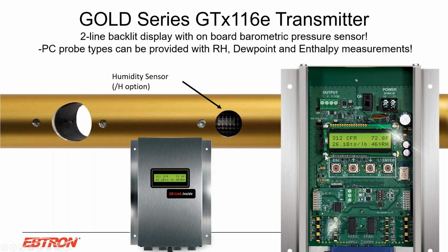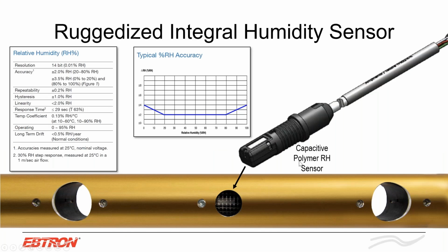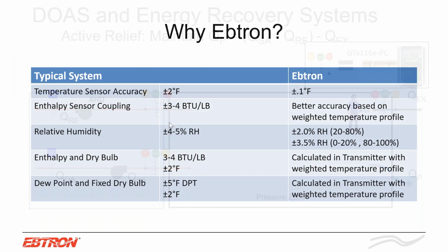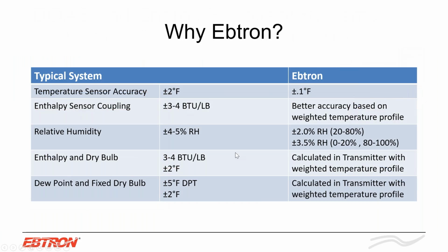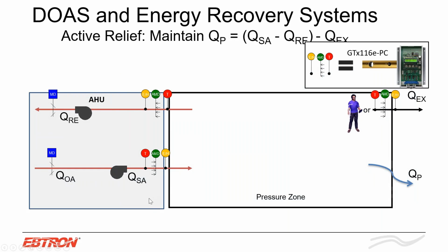So as an ATC contractor, this is a way to help save money. Instead of buying a separate outside air sensor to put in your outside air intake, utilize the 0.1 degree F sensor of the EBTRON unit, or utilize the relative humidity sensor of the EBTRON unit. Now, if you're doing any type of economizer control strategy, we can help you out with that. And we can help you out with pressurization control as well. So this is just maintaining active relief. This is for a DOAS or energy recovery setup. And you're maintaining the pressurization between the supply and return, right? Because we don't want to have pressurization control option issues. And again, we can also read your temperature, flow, and humidity or enthalpy.